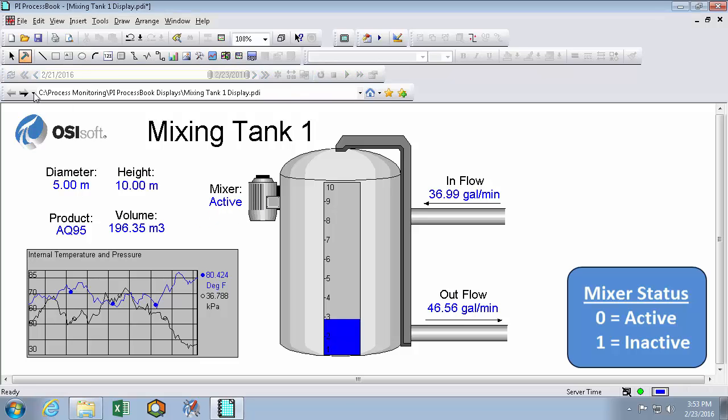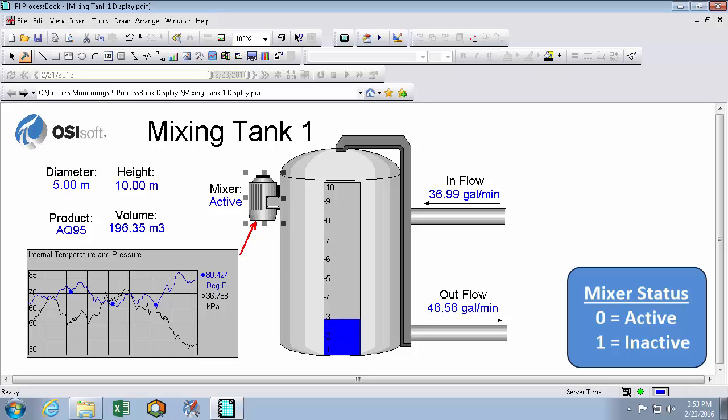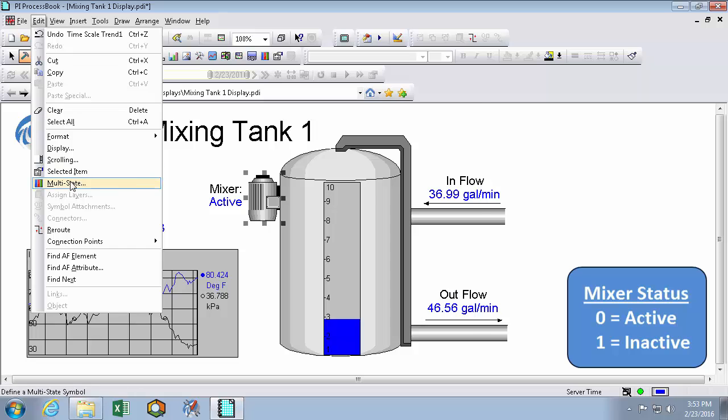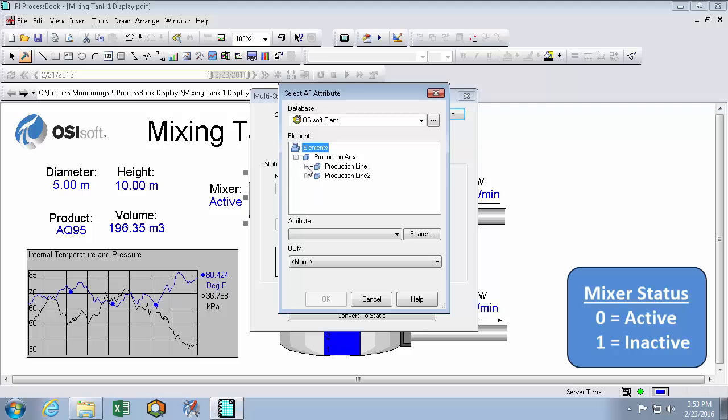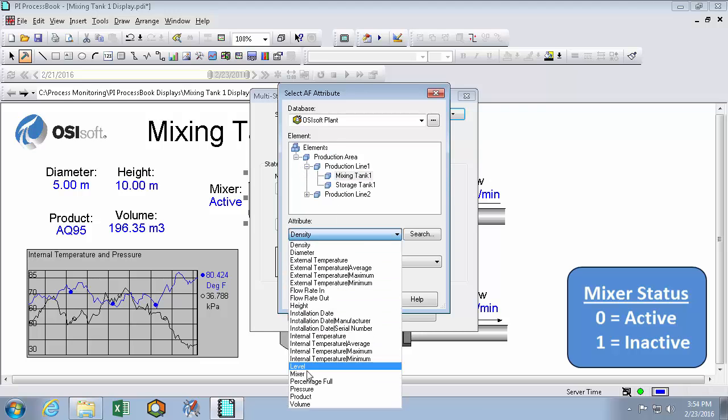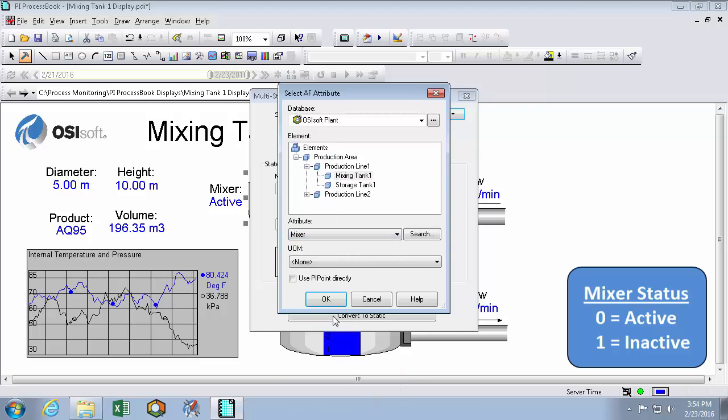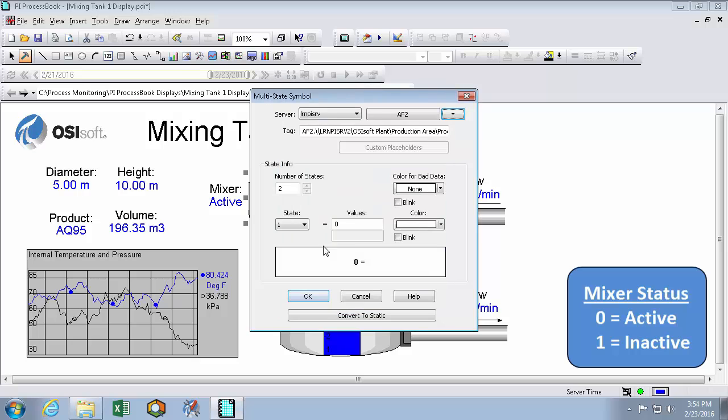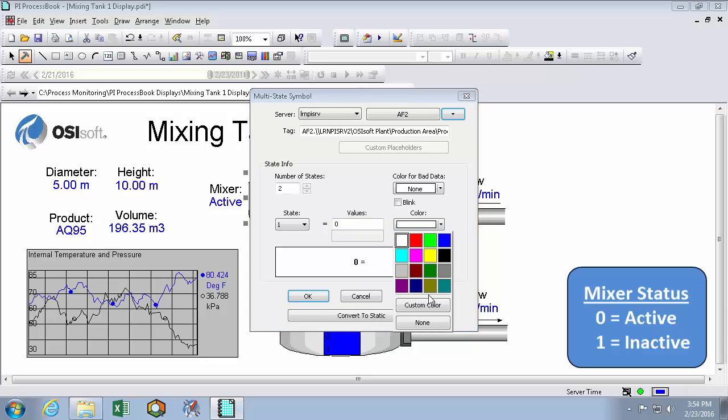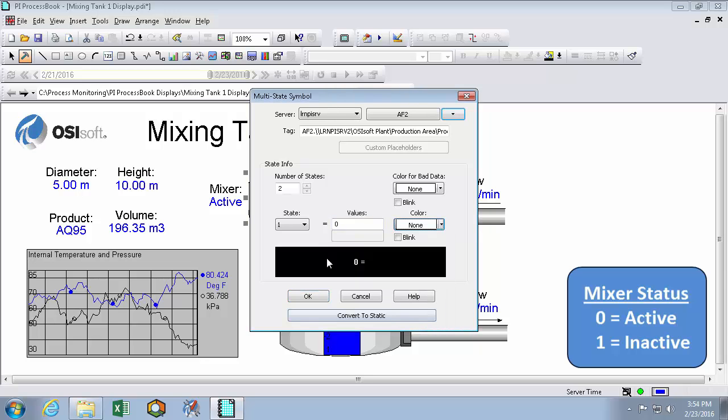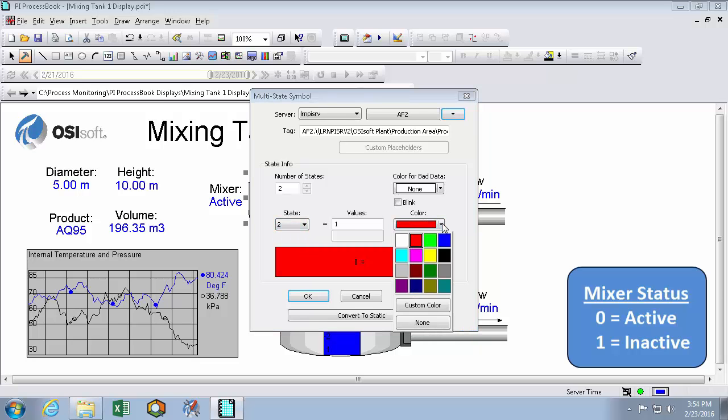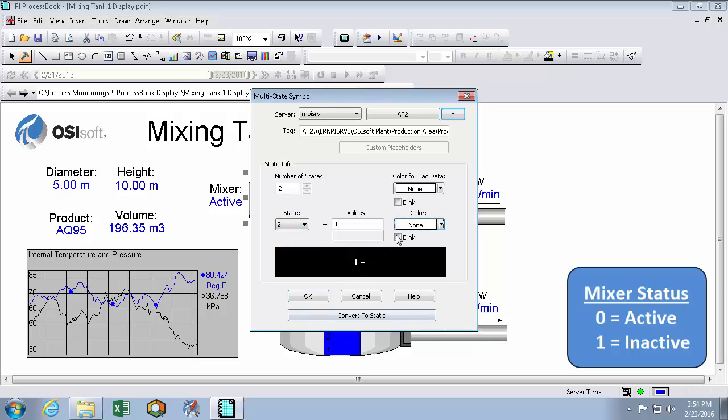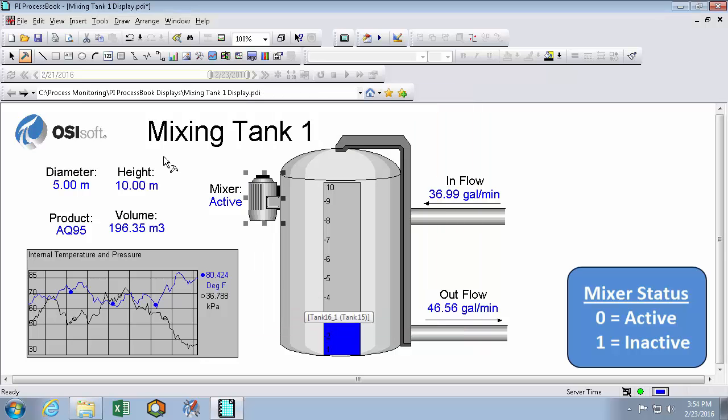The next thing we'll do is go back into build mode and select our mixer. And we can convert this static symbol into a dynamic multi-state symbol by editing its multi-state. And we'll repeat a similar process using mixing tank 1's attribute called mixer. And it'll still have two states. Remember the first one is active. And we'll remove the color change from this state. And in state 2, we'll also remove the color change, but we'll make it blink. So I'll hit OK.